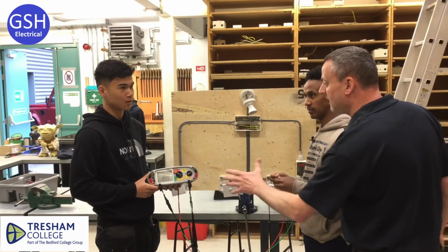Joe, which test are we going to carry out for me now? Continuity of CPC. Good. What does CPC stand for, Abil? Circuit Protective Conductor. Which test will be included at the same time, Joe? Polarity test. Of all the readings we get, which one will we record? The highest. And where do we expect that to be, Joe? Furthest point of a line. Furthest point, because the circuit is wired allegedly in what form? Radial. Yeah, we've got a bit going on with this lighting circuit, but still a radial circuit. Okay, so let's get ready for that test.